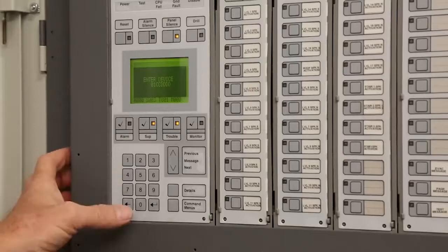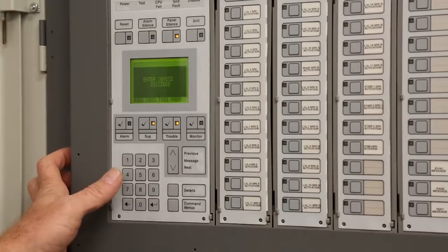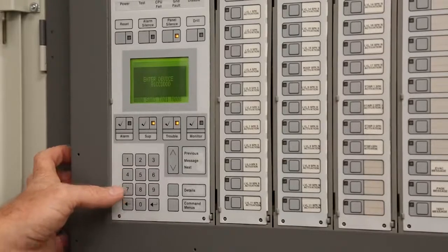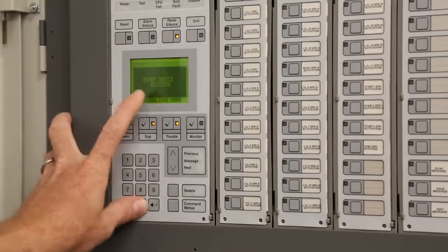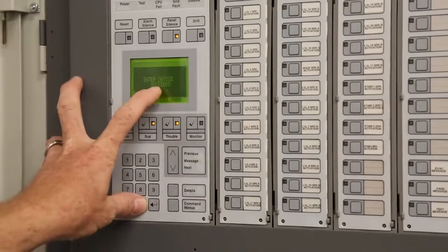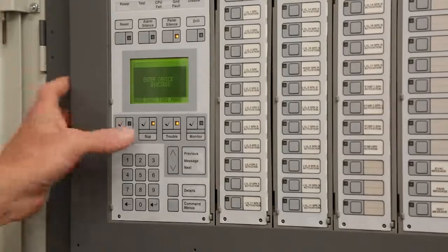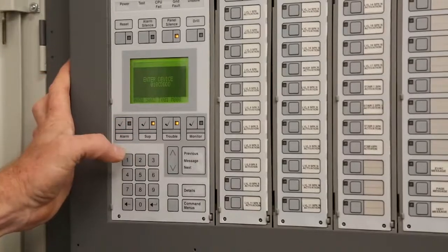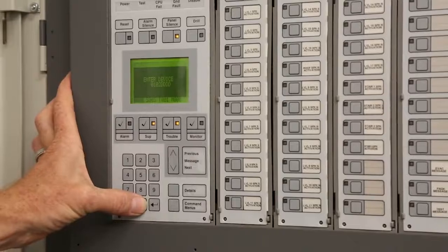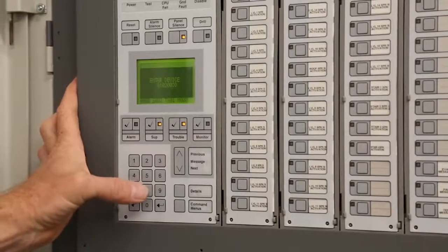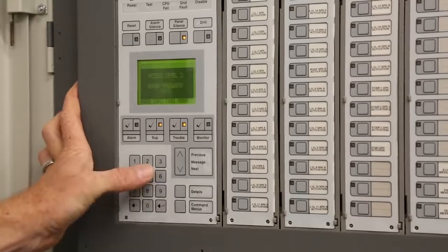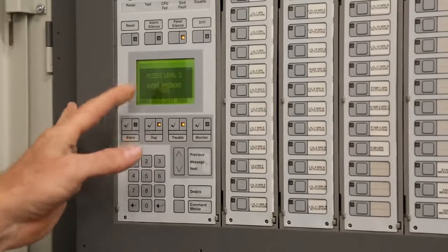Okay. So if the detector on there, for instance, I believe this one is panel 1, card 2, device 38, you'd have to fill in on the numbers. So if it's card 2, you see there's 2 C's there, you have to fill it all the way in. You have to fill it completely in. Basically, we'd have to go 2, 0, 2, and if it's 38, 0, 0, 3, 8. Hit enter.